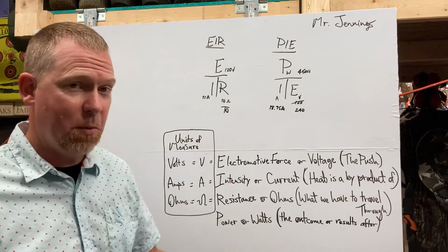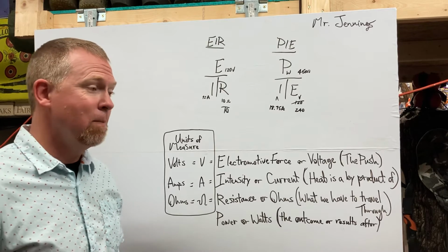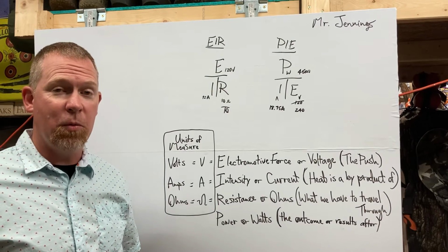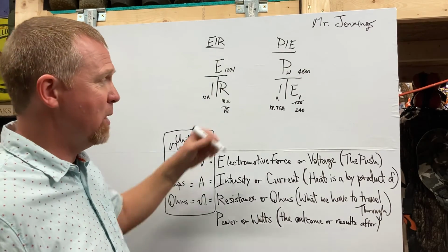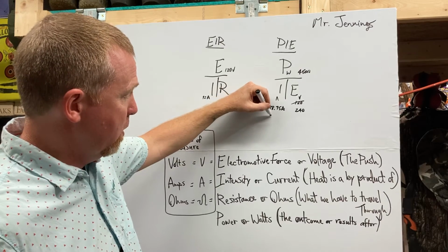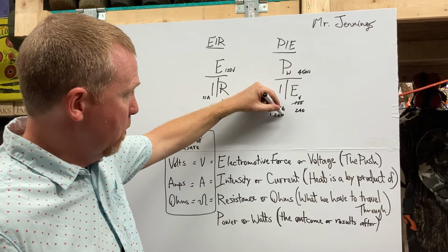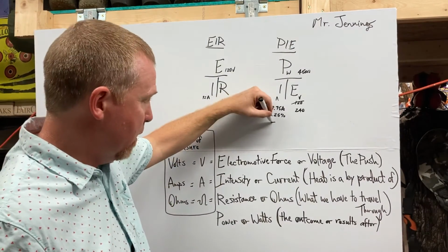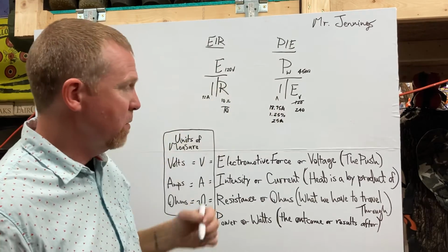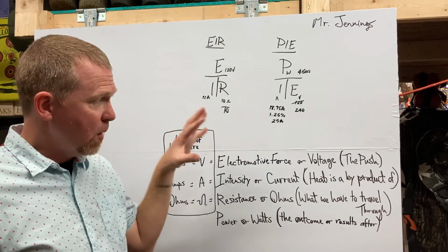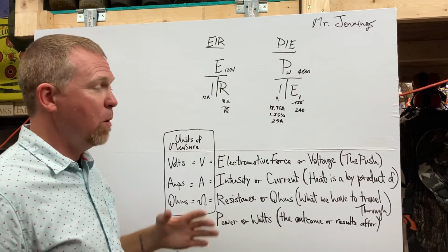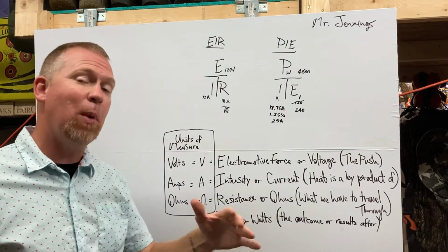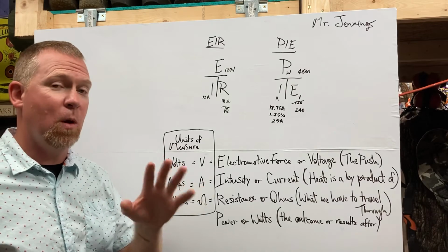And there are other steps that would come into play when we're dealing with constants. If something's considered continuous duty, if it's running for over 3 hours, we have multipliers that we take into consideration. So we would multiply that times 125%, which gives us a value of roughly 25 amps. And we have standard size breakers that we would utilize in determining what size breaker we need in the panel to provide enough power for the circuitry involved for that water heater.